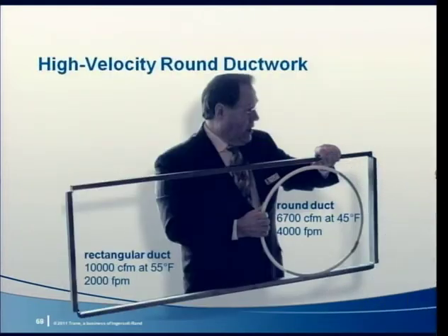To wrap up the discussion of duct sizing, there is a way to get this energy savings and still reduce ductwork installed cost. Round ductwork allows you to design for higher velocities and allows for the use of the static regain duct design method. Combined, this can significantly reduce the amount of sheet metal, often saving $1 to $1.50 per square foot.